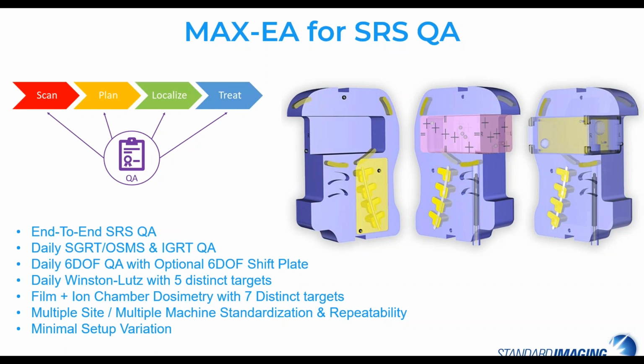It can be used and compatible for SGRT or OSMS system with the camera tracking. With the optional 6-DOF shift plate, you can also do a daily 6-DOF QA. We also include with the Phantom a Winston Lutz insert, which has 5 distinct targets. And Phantom is also unique in that you can use multiple modalities for dosimetry. There's film, and there's also ion chamber.